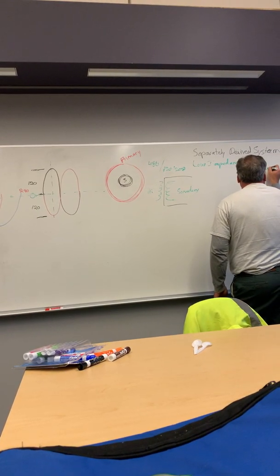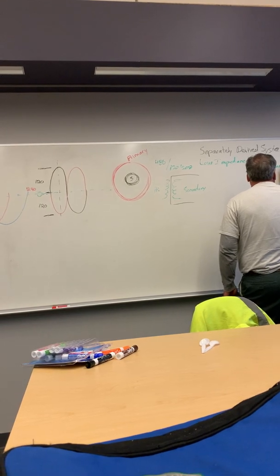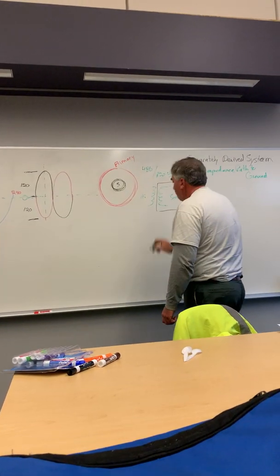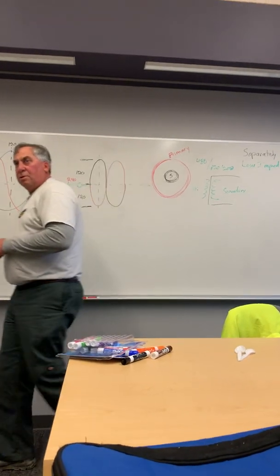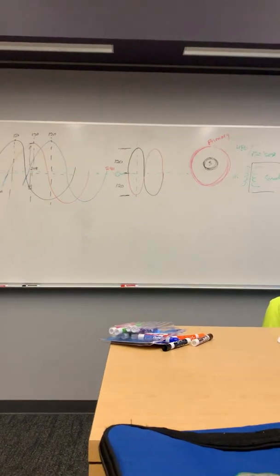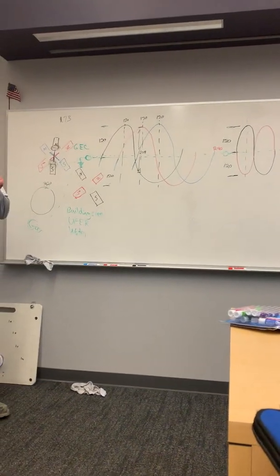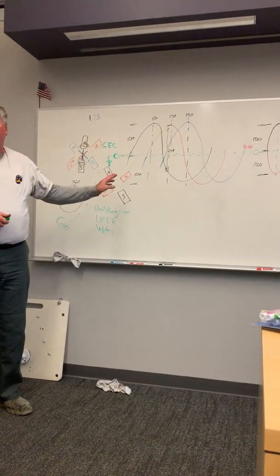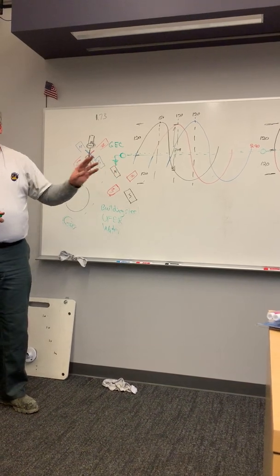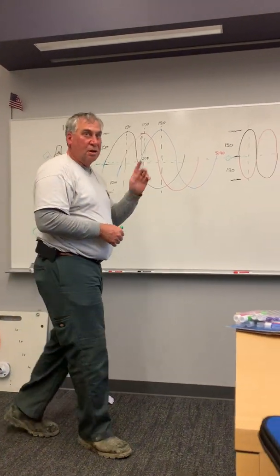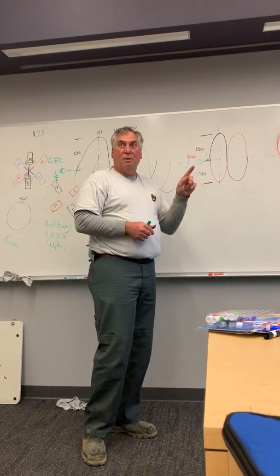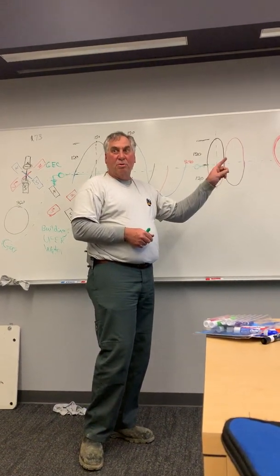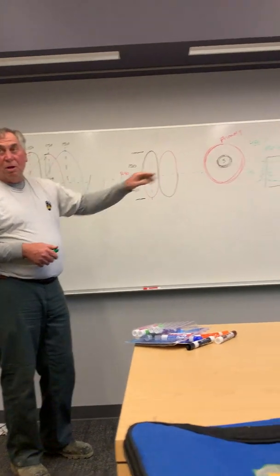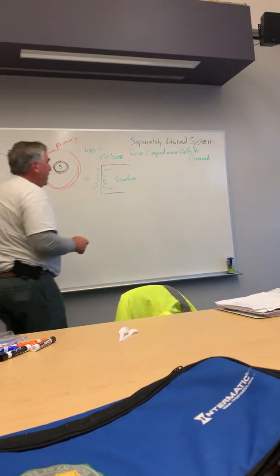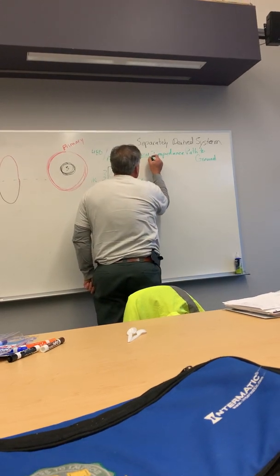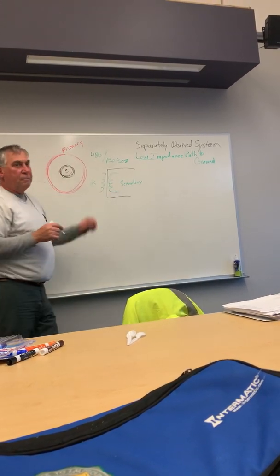And why would we want to do that? Why would we want to keep this low impedance path to ground as low as we possibly can? We want to make sure that it is the shortest path for the current to trip the overcurrent protection, to keep it safe, because our whole purpose in the code is the safe use of property and people. So this is the one thing we want to do: keep a low impedance path to ground.